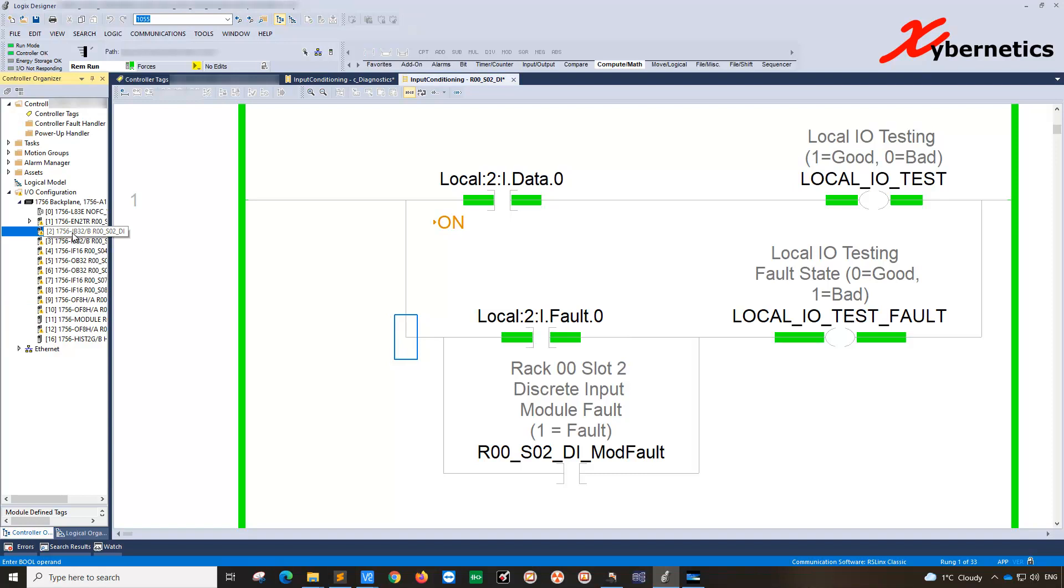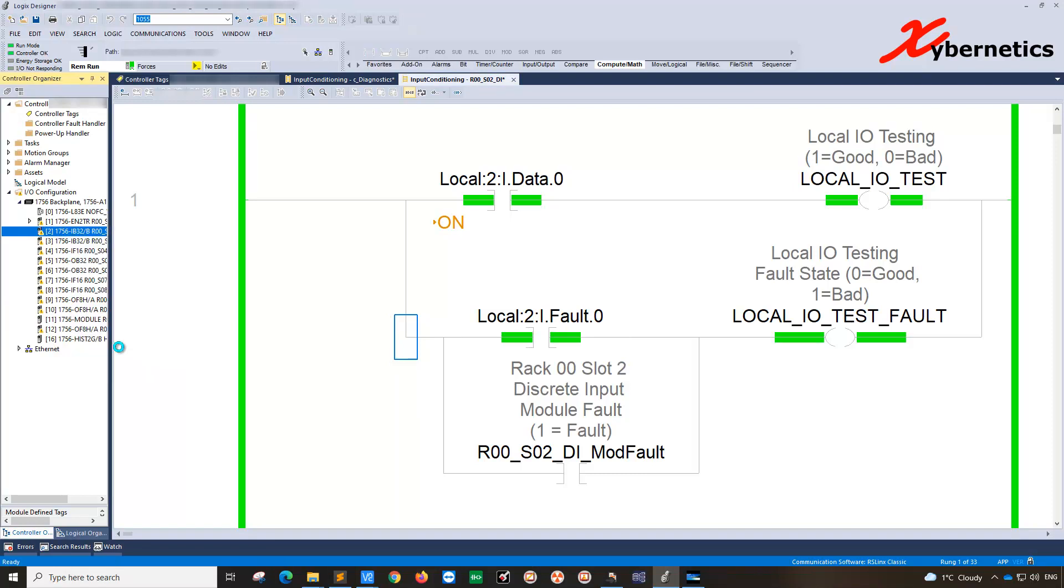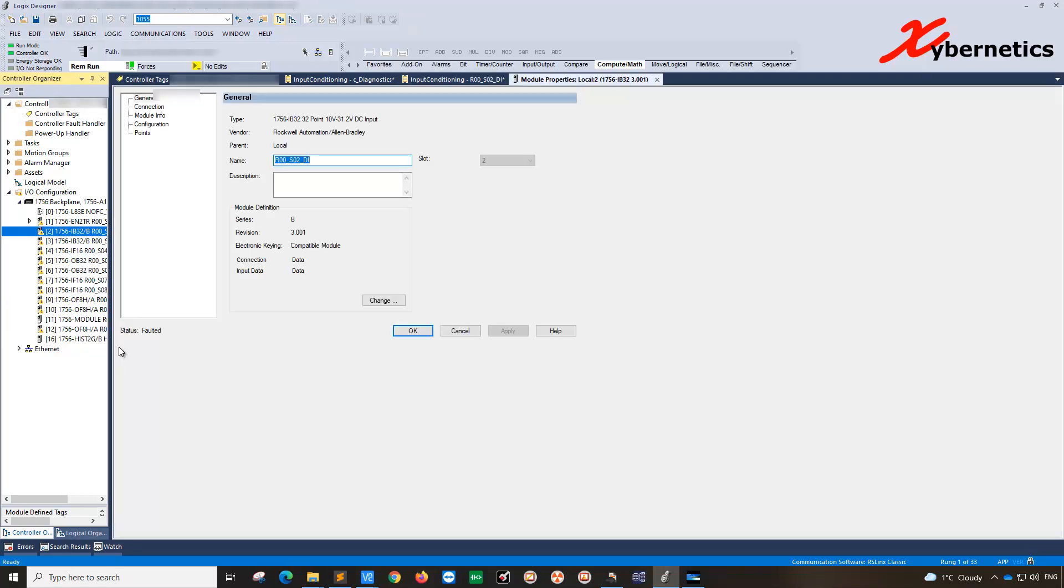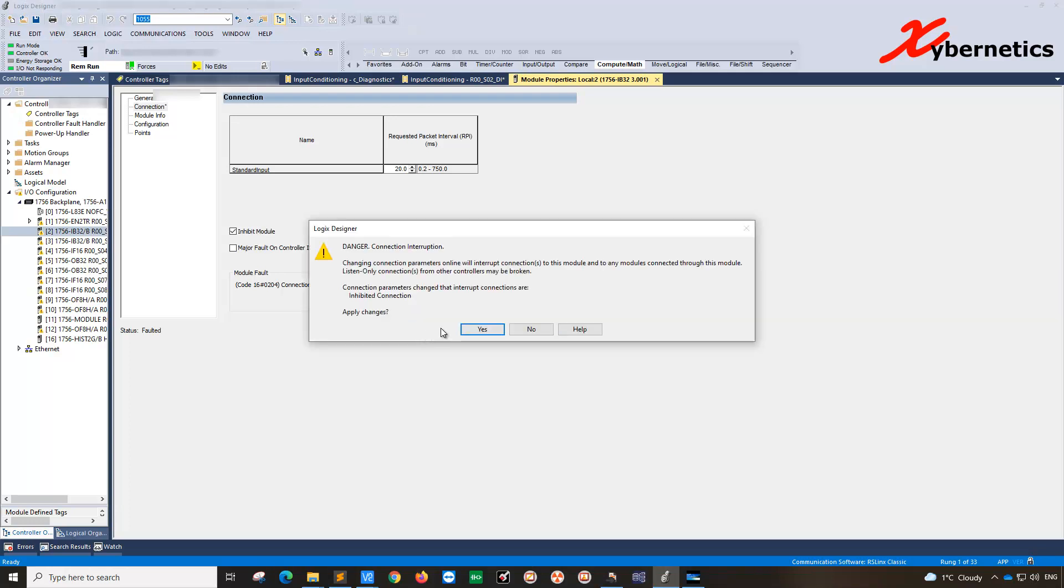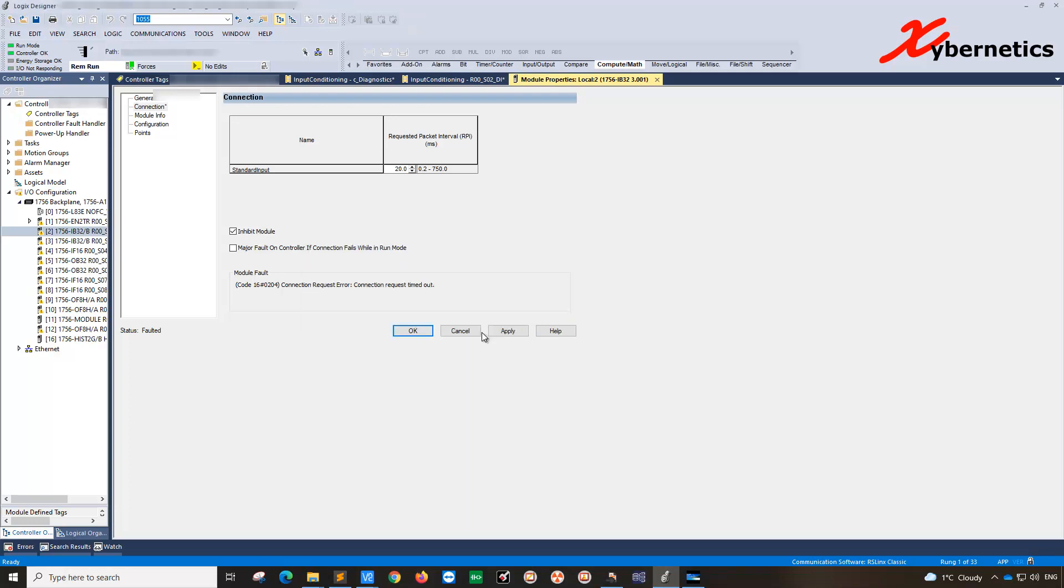This is in slot 2 channel 0. Slot 2 is this guy here. Right click and go properties. Under properties go to connection and go inhibit module. What inhibit module does is it inhibits the module, essentially all the IO and the channels in that particular module will be ignored and will be told that all the wiring are good.